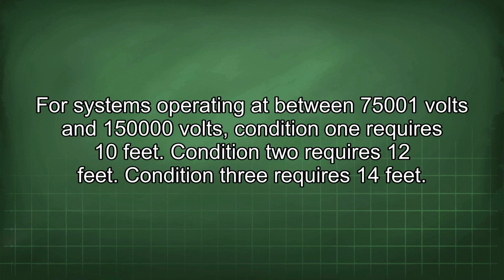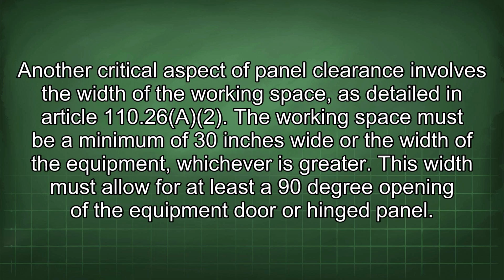For systems operating at between 75,001 volts and 150,000 volts, Condition 1 requires 10 feet. Condition 2 requires 12 feet. Condition 3 requires 14 feet. Another critical aspect of panel clearance involves the width of the working space, as detailed in Article 110.26(A)(2). The working space must be a minimum of 30 inches wide, or the width of the equipment, whichever is greater. This width must allow for at least a 90-degree opening of the equipment door or hinged panel.